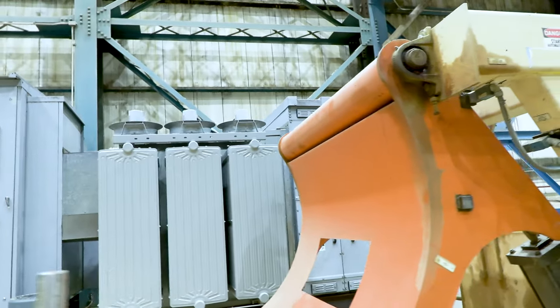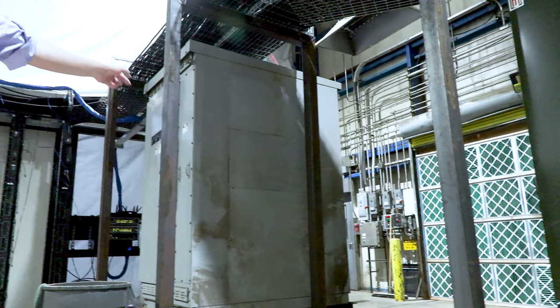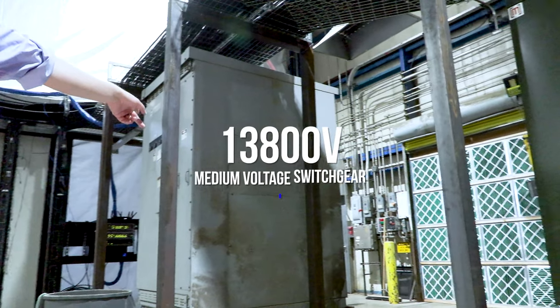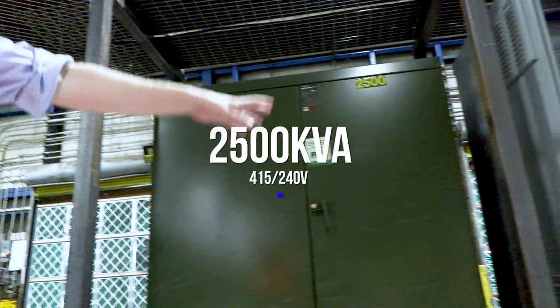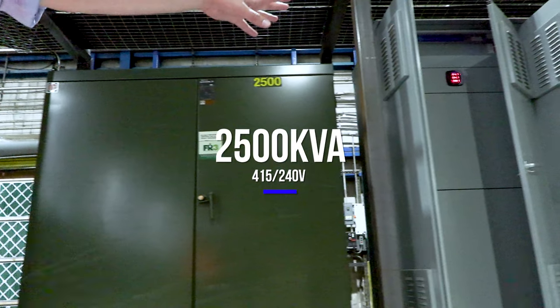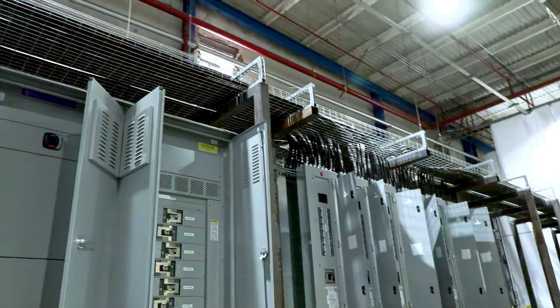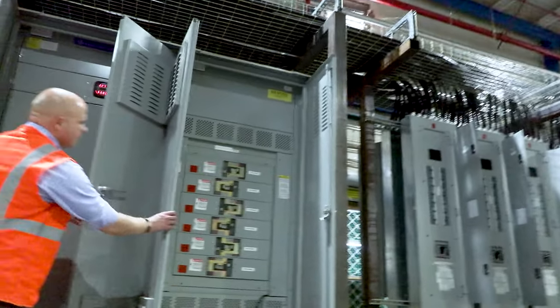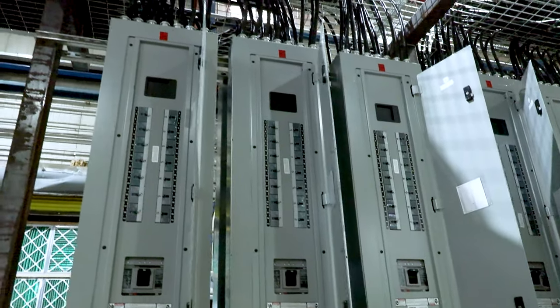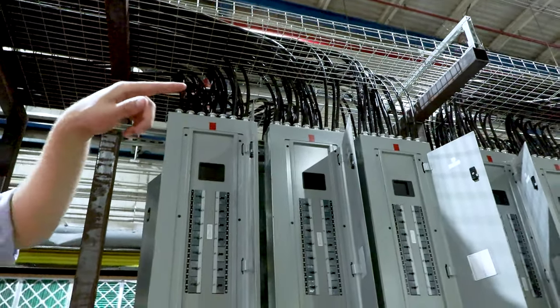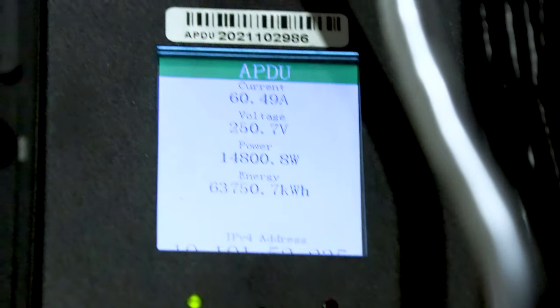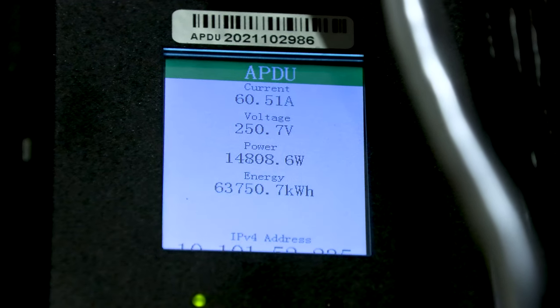Now let's peel back this setup. This was running in from a 13.8 high voltage side coming into a 2500 kVA transformer, which steps that down to 415, 240. That then comes into low voltage switch gear, which sets up the power panels hosting an array of 125 amp breakers, and those breakers feed over to the 125 amp PDUs.